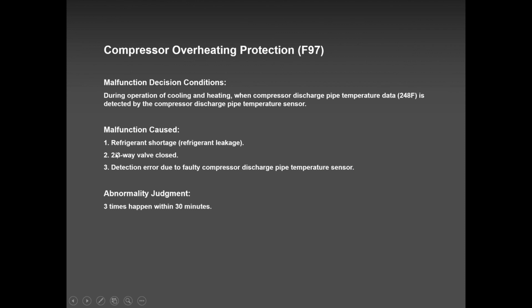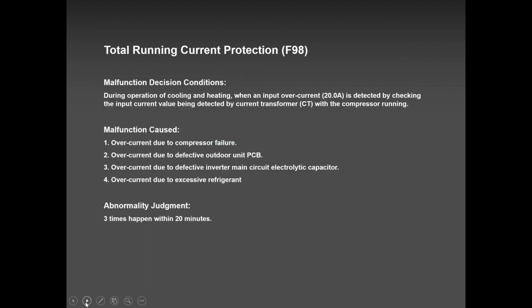Very rare to see a 3-way valve closed. In most cases, when you're done with vacuuming, you check that you're maintaining good microns, you release the gas and you release on both sides. Very rare. I have come across maybe 1 or 2 jobs where the guy forgot to open up both valves. They opened only the suction and forgot to open the liquid. I don't know why, I don't know how, but it can happen. Or refrigerant shortage.